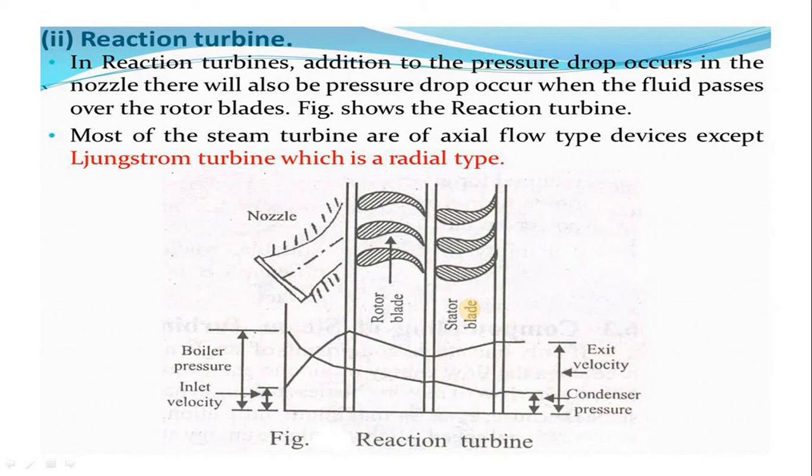It acts as a nozzle also. So here, whatever steam from the boiler enters the steam turbine, before that, in the nozzle, the velocity increases, that is, kinetic energy increases by reducing the pressure energy. After that nozzle, the high velocity steam, with high kinetic energy, enters on the surface of the blade.